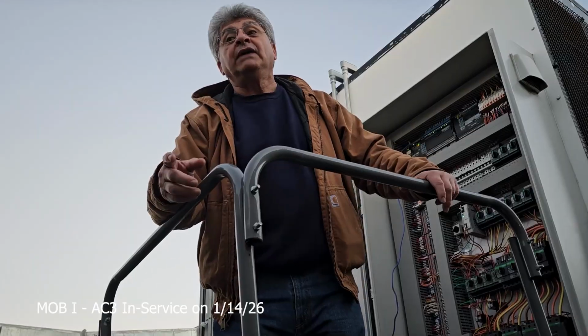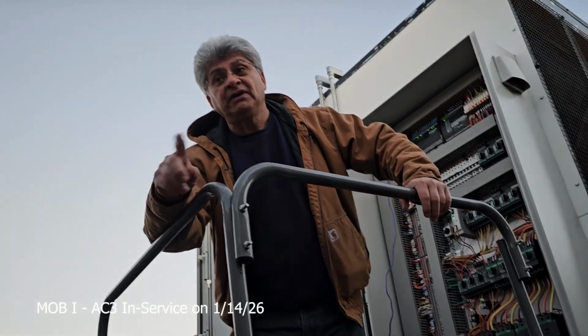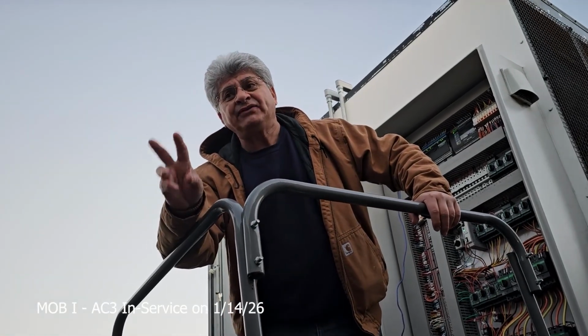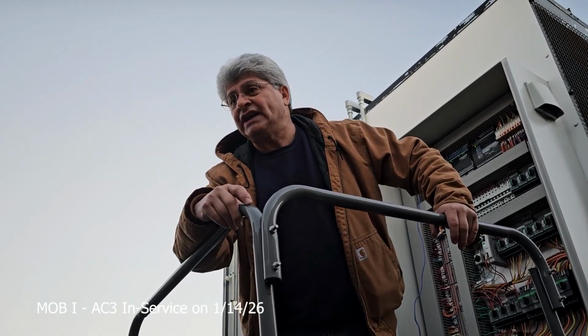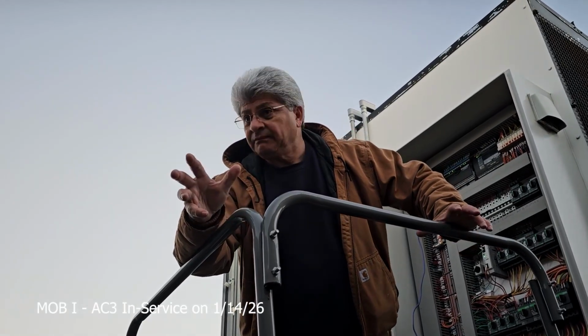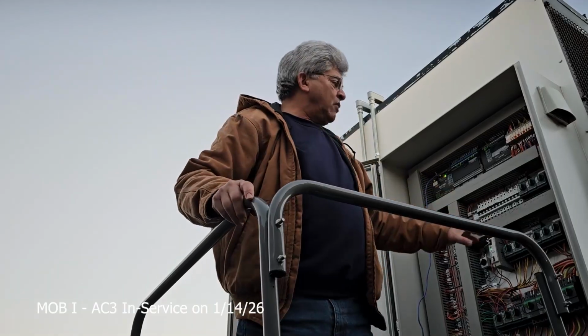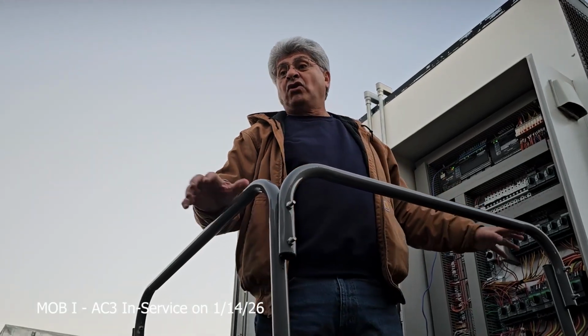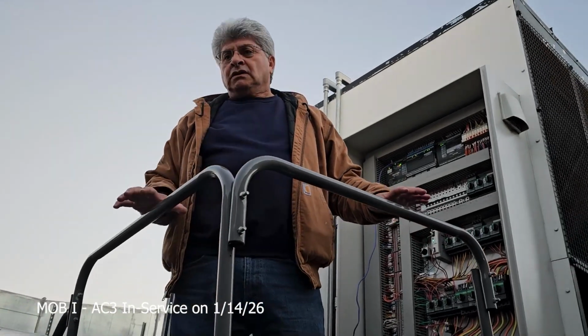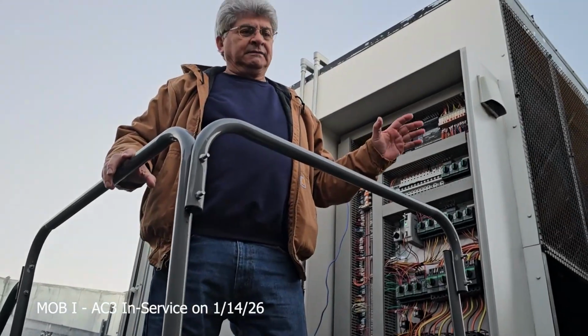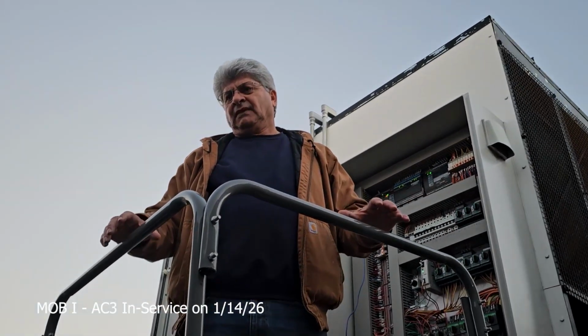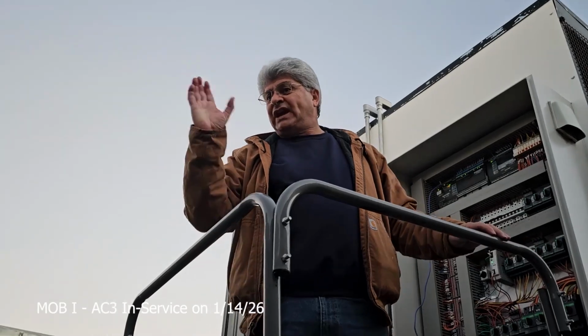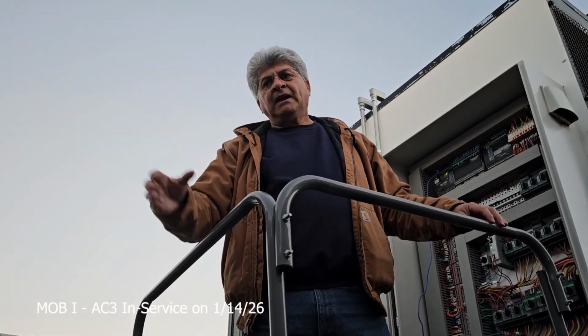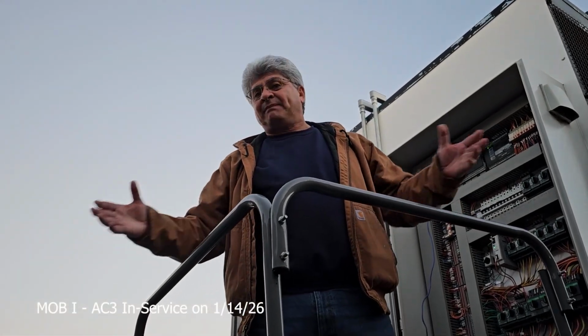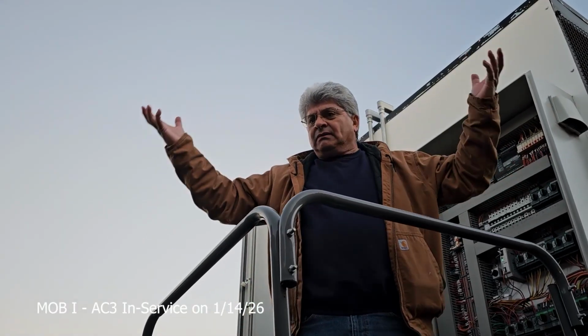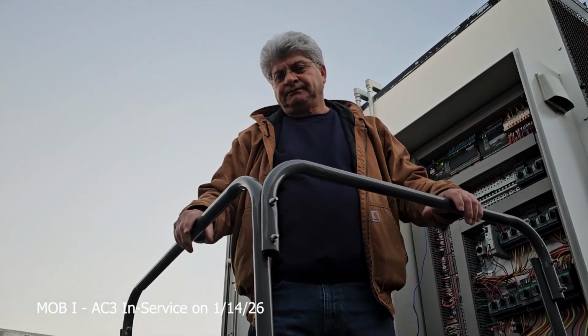Now, if she's off in the middle of the summer for an hour and a half, 2 hours, like a breaker trip or something like that, if something happened that caused the entire machine to shut down, all your fans, once you get it back up again, you've got to give it time. Your cooling circuit will maintain your supply temperature set point, but your static will be dictated by your VAV boxes and your load in the building.